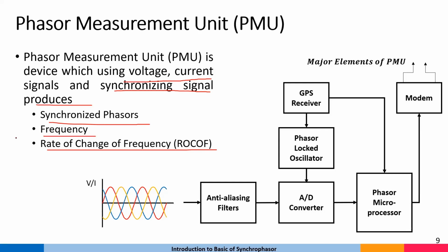So this is like in the field we have this kind of setup. We have current transducer and voltage transducer in the field, called current transformer and voltage transformer. The voltage transformer goes to an anti-aliasing filter, then an analog to digital converter. Then we have a GPS receiver and phase lock oscillator, which provides time synchronization. Then we have a phasor microprocessor, and what it does I will tell you.